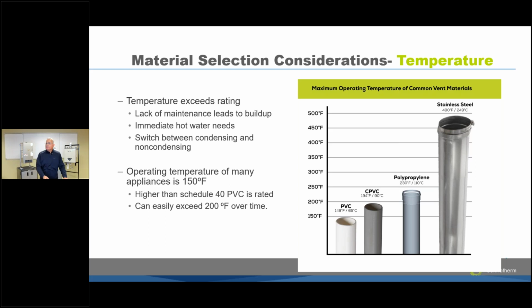Yes, sir. Yes, so we have another question here. Gentleman asks, have you seen the Centrotherm pipe crack throughout the years while in use? He's talking about he had a Viessmann concentric kit where the inner pipe broke apart, causing the gas to recirculate. So have we seen that? I have not seen that, and I'm not saying that because we represent the company. I truly have not seen that.